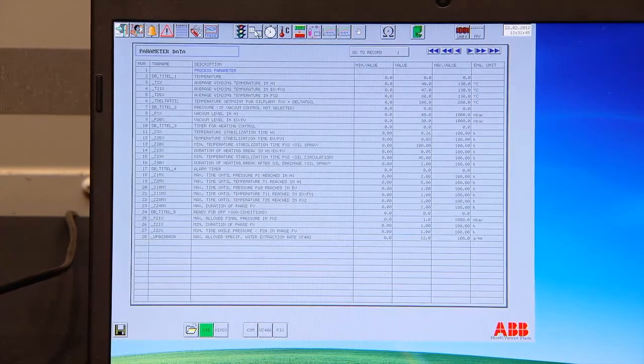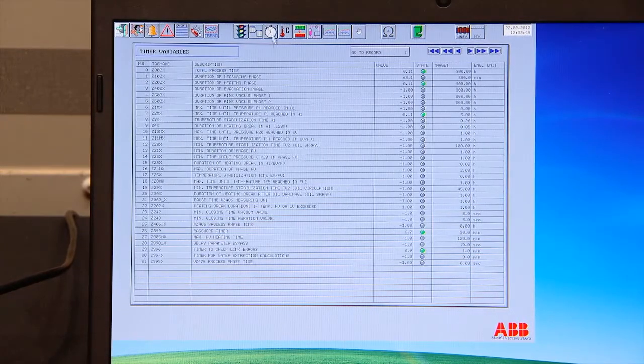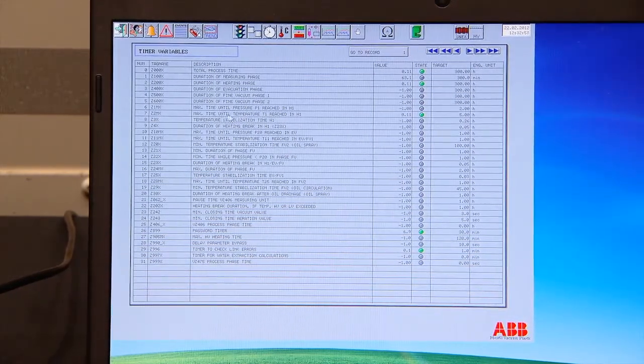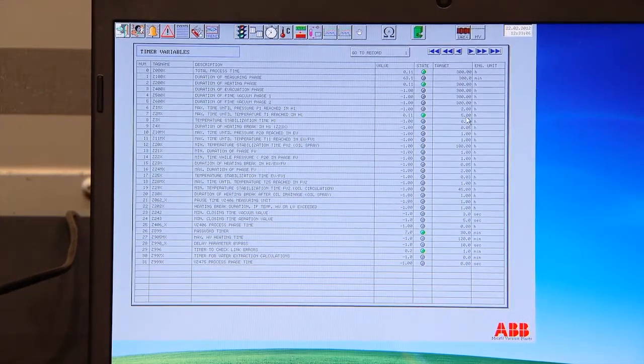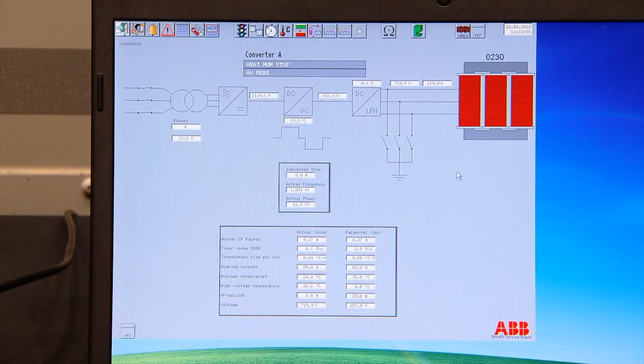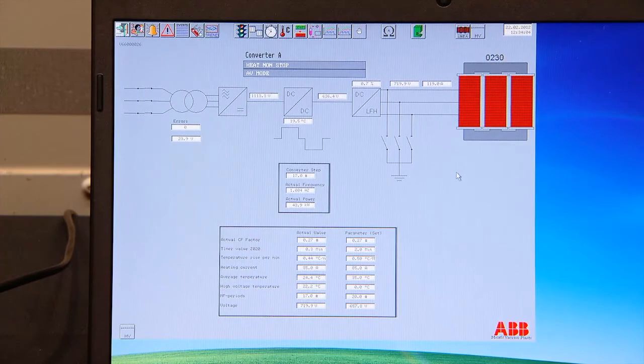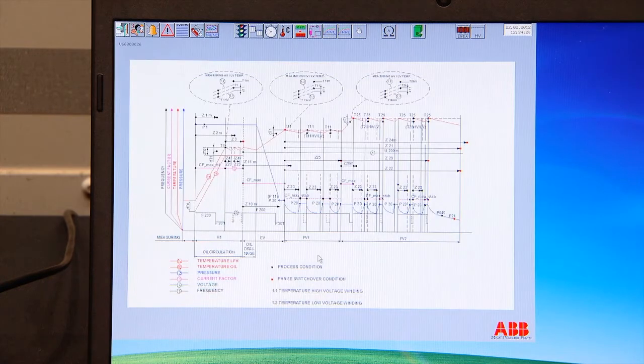Remember from yesterday, I showed you that there are timers on this button with the pages. There is a timer here called set to MX, maximum time until temperature T1 reached in heating. So if you're not reaching your temperature here within 5 hours, then he will give you an alarm. Now you go up to 20, you go up to 90 degrees, and then you will do a stabilization period. So you will do some reheating up to 90 degrees, then you have a heating break of about 2 hours, then you reheat again to 90 degrees, then you have another heating break of 2 hours. Doing that over a period of time, let's say 12 hours or 24 hours, you're stabilizing at your level at 90 degrees. So if I come in and it's at 80 degrees, I want to go to 90, yep, I should be able to do that within 2 hours.